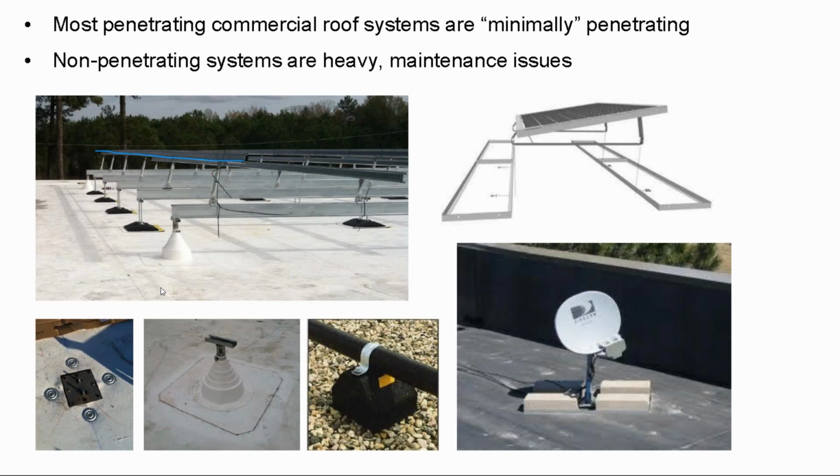I don't think any of those fires burnt down the building. But there have been some other notable fires that have burned down buildings, Dietz Watson being one of them. And that major failure point was caused by the conduit on the rooftop.